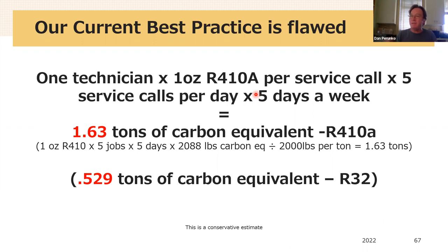And then they let the refrigerant out of their gauges because that's what they've been trained to do. And every time they do that, they're releasing 3 to 9 ounces of refrigerant. So to be really conservative and make sure nobody gets too mad at me, I did the math for this example using 1 ounce of refrigerant leaked every time there's a service call.